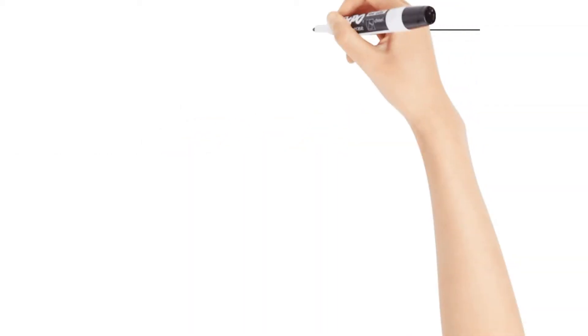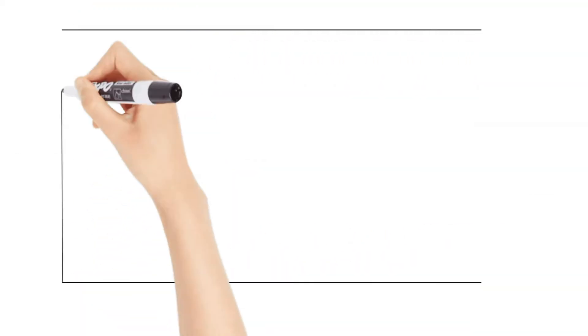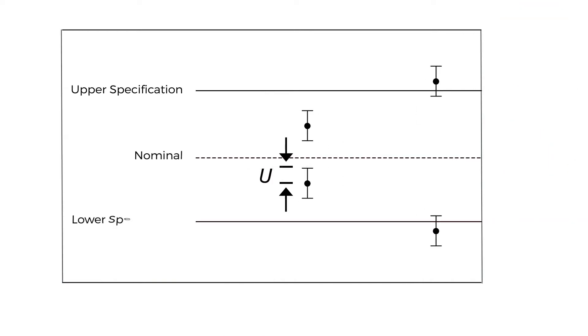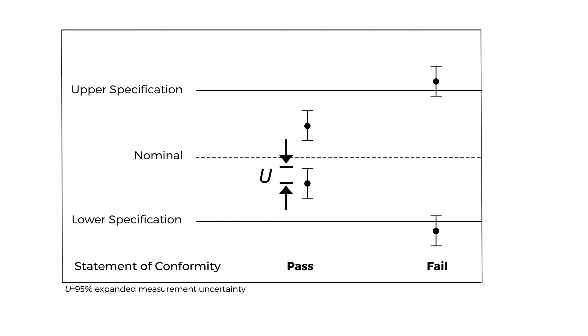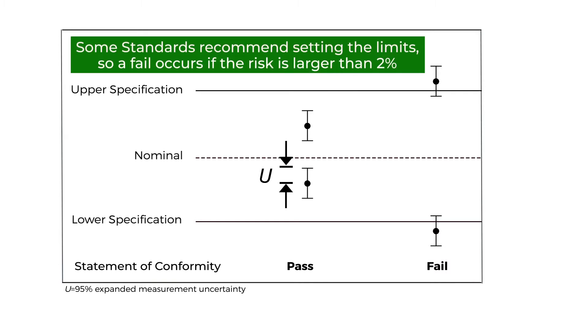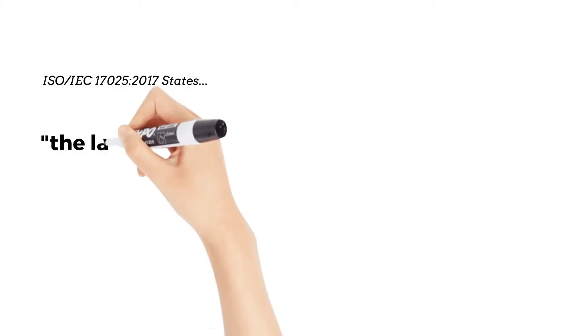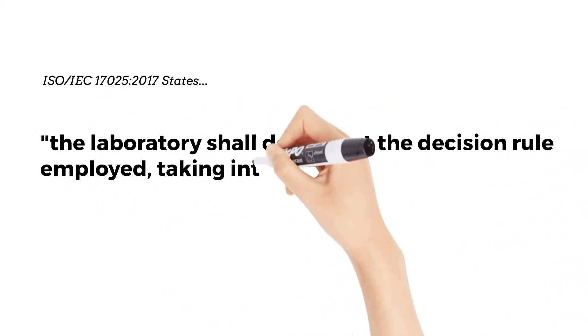Decision Rules and TUR. When discussing decision rules, we describe how measurement uncertainty is accounted for when stating conformity with a specified requirement. The conformity for most is binary, meaning either a pass or a fail, and some standards recommend setting the limits so a fail occurs if the total risk is larger than 2%. The laboratory shall document the decision rule employed, taking into account the level of risk.